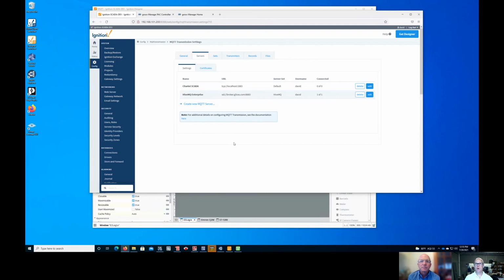And that works great for flat MQTT, because you can prepend all of that. So if you have your area MQTT structure, you can prepend that up and go to your site. But you can't do that with Sparkplug B, because it's the group and that node ID that dictate everything that's there. So all you're going to end up with is it'll prepend it, but you're still going to have that Sparkplug B v1 namespace that sits in the middle, and that's exactly how it's going to ignore everything that's in front.